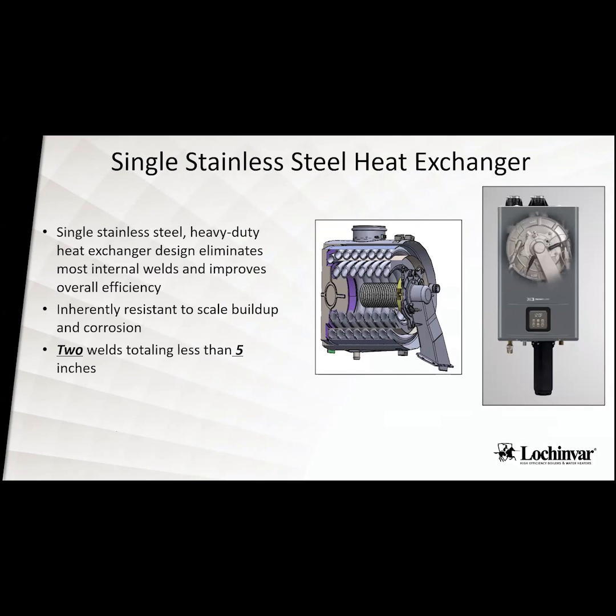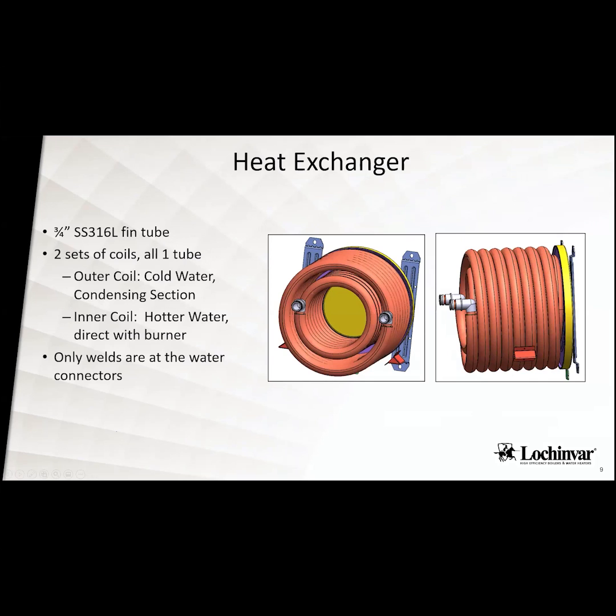So talking about the heat exchanger, this is a very heavy duty heat exchanger. It's 316L austenitic stainless steel. It's a water tube design that's built into that unit. So this unit will be about 15 to 20 pounds heavier than any other tankless on the market because of how heavy duty that heat exchanger is right there. As you'll see right here, there's your inlet and your outlet. There are only 2 welds on this whole heat exchanger. So it is a water tube heat exchanger.